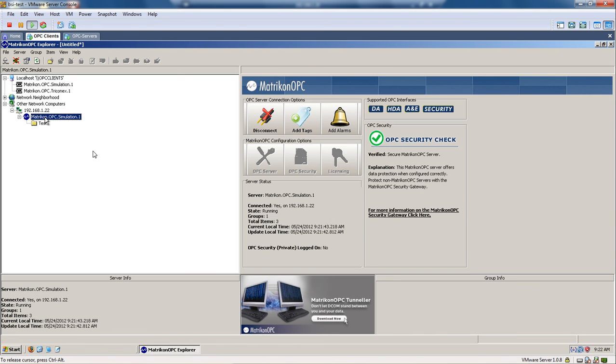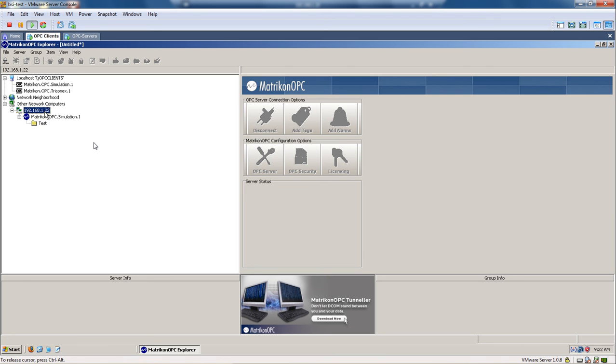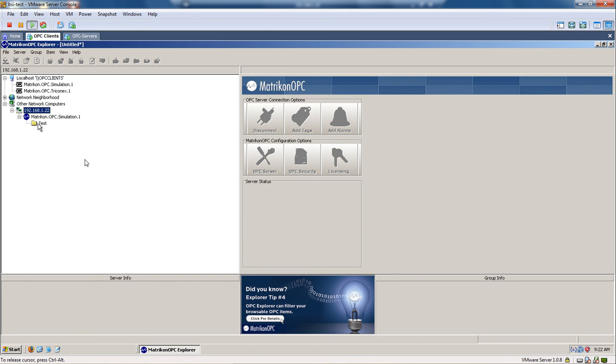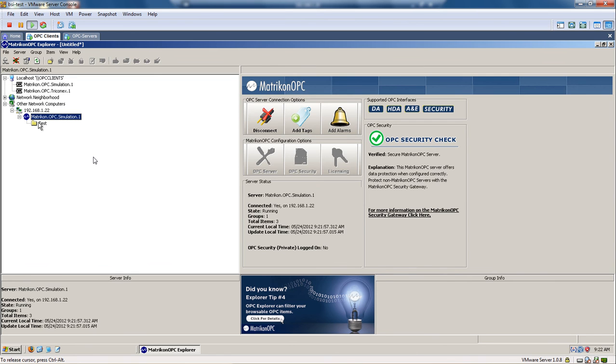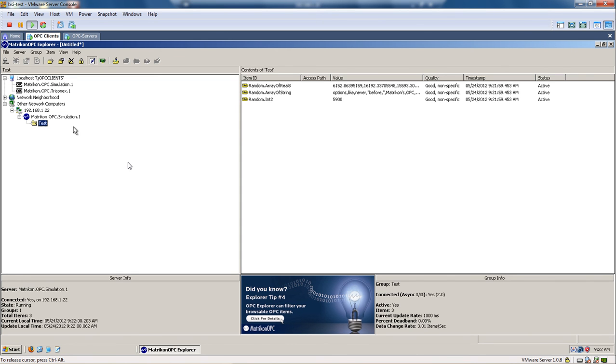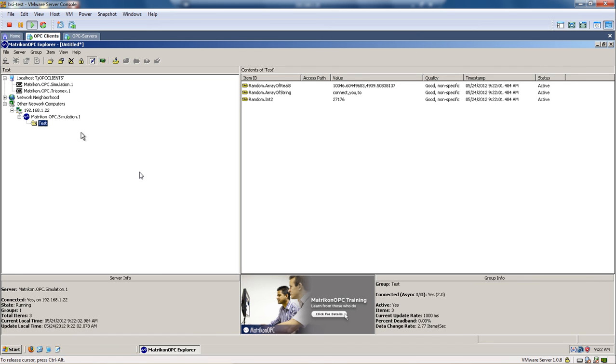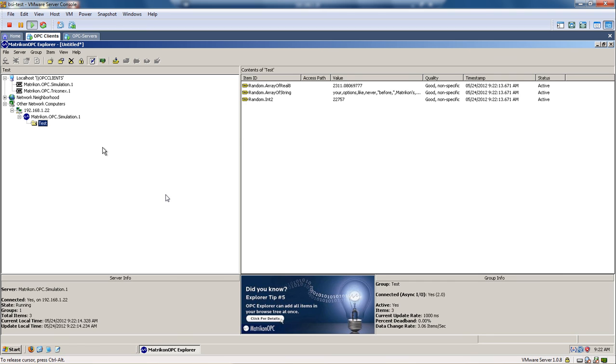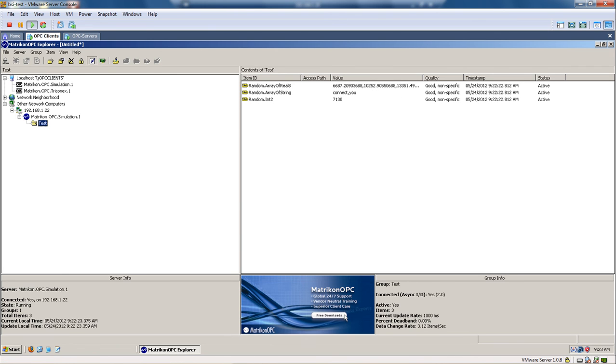So when we're putting Tofinos in front of industrial controllers, those controllers never use NetBIOS protocol. And in those cases, we can simply block the NetBIOS protocols and consider them to be more or less of a nuisance protocol that doesn't help us in that part of the network. However, when we're putting a Tofino between two Windows PCs, and specifically when it's going between an OPC client and an OPC server, very often we must allow those NetBIOS protocols to pass between at least those two Windows PCs in order for services like OPC to work properly. So how do we set that up in Tofino CMP?